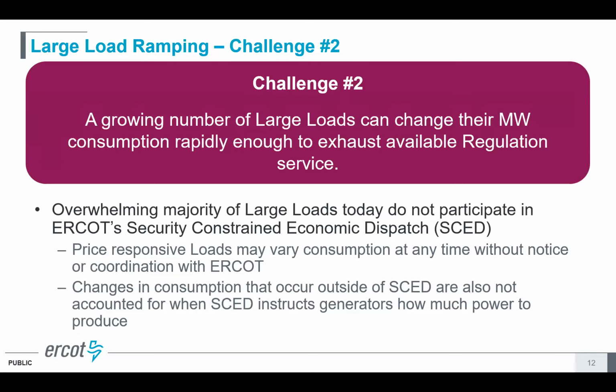The reason this happens is because the overwhelming majority of these loads are operating outside of the economic dispatch, so they're not participating in SCED, which means SCED isn't accounting for that ramping behavior because there's no way to predict it, and doesn't factor that in when it dispatches generation. So when the ramp does occur, it has to be covered by frequency regulation.